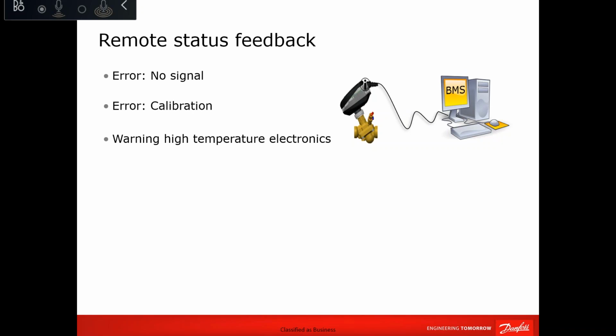Also, you will have an alarm if there is a high temperature inside the PCB of the actuator. If there is abnormal power supply voltage, this is also very important. Why? Because you would know where exactly to boost the power. Let's say if you need to boost the power in a loop, we say that it should be every 7 to 11 actuators you need to boost the power. It might be more. How do you find out? By this alarm, if there is abnormal power supply voltage.